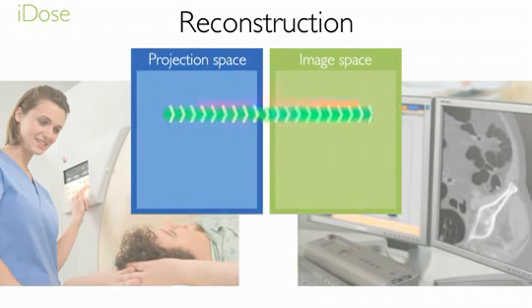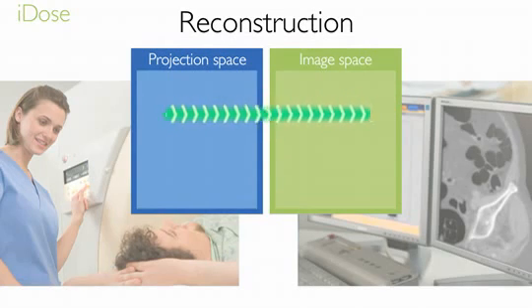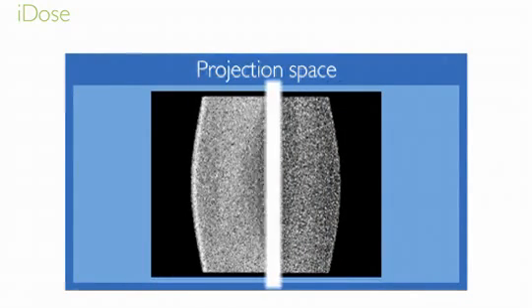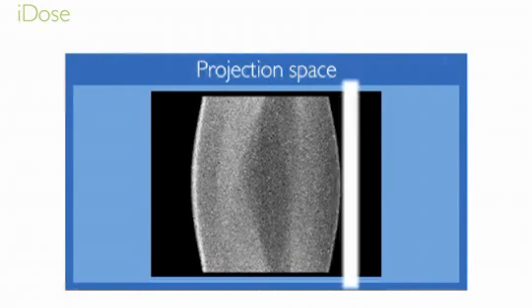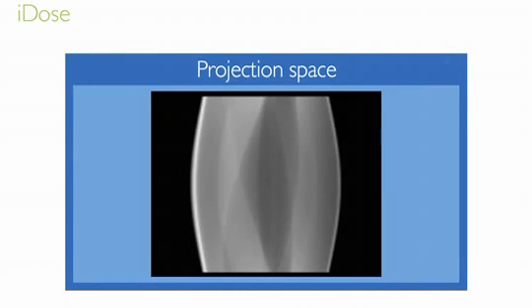Reconstruction is the process of converting acquired data into images — that is, it is the process of transitioning the data from the projection space to the image space. iDose uniquely takes advantage of the inherent properties found in each space. In the projection space, noise is removed iteratively from each unique projection. This step is critical as noise present in the projections would ultimately translate into streaks on the final images. Without iDose, these streaks are often seen in low dose imaging.